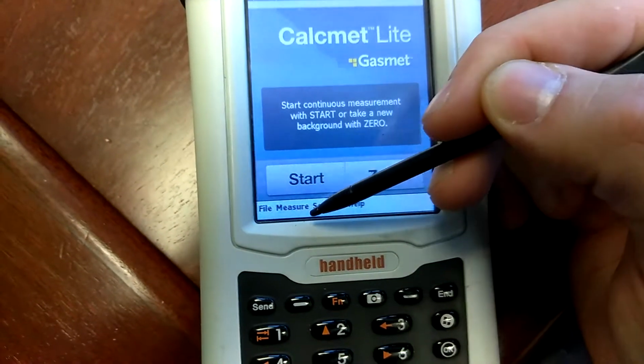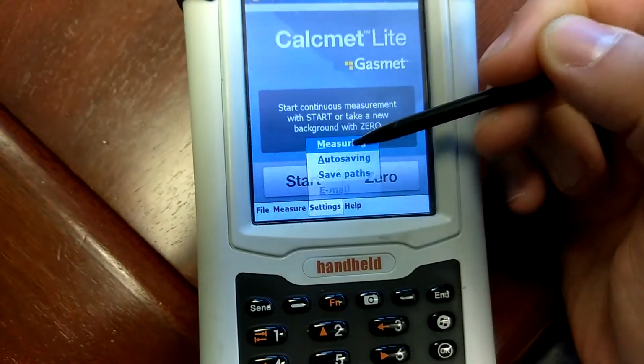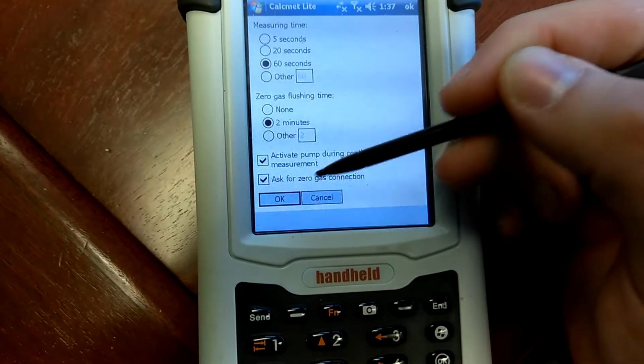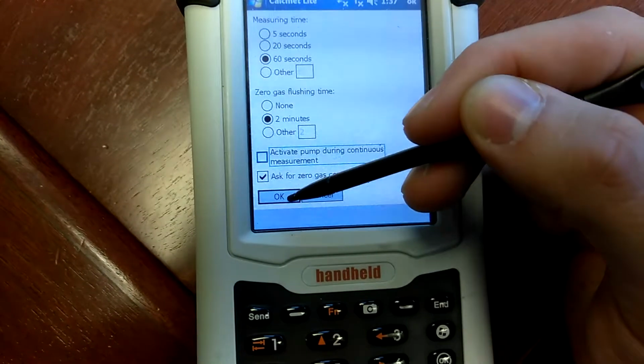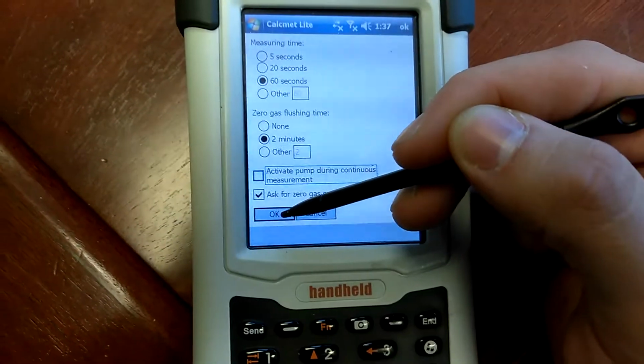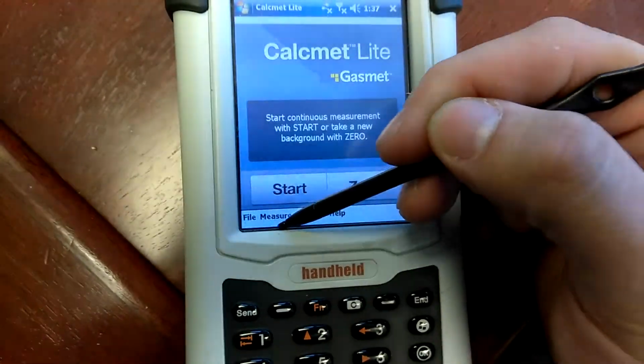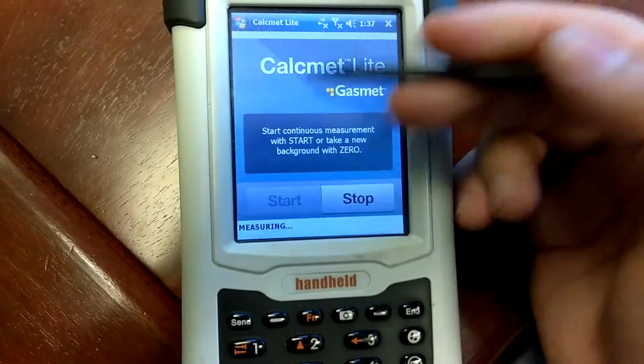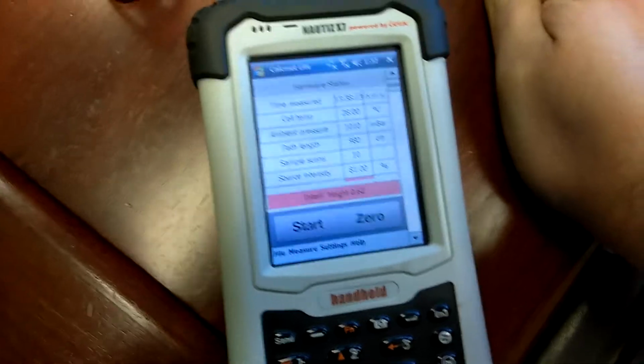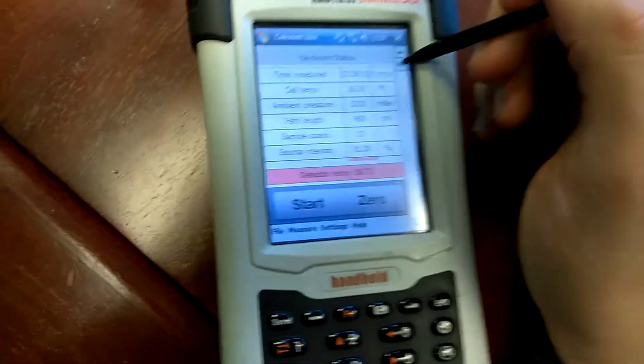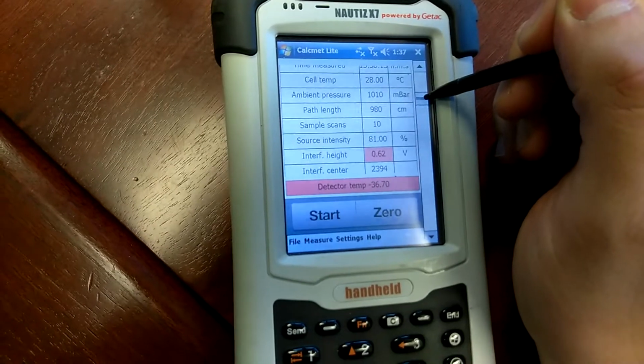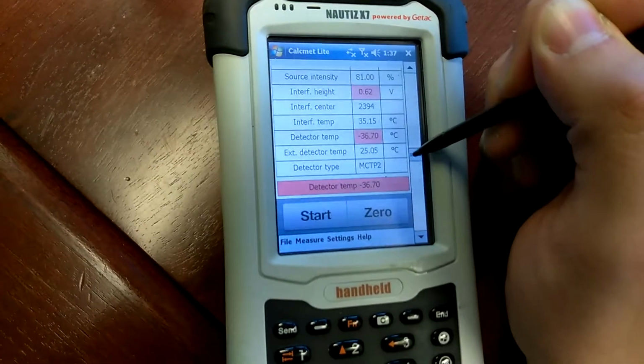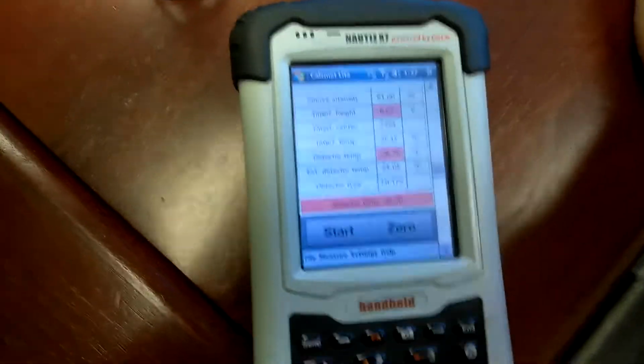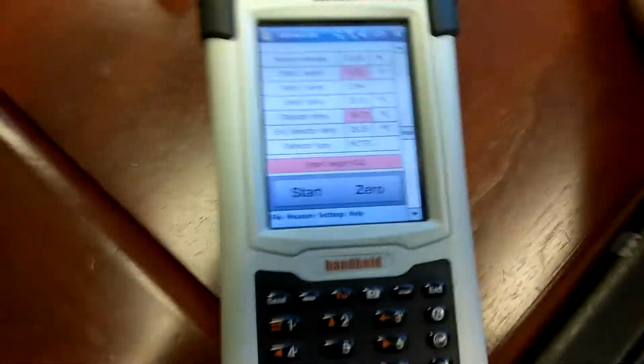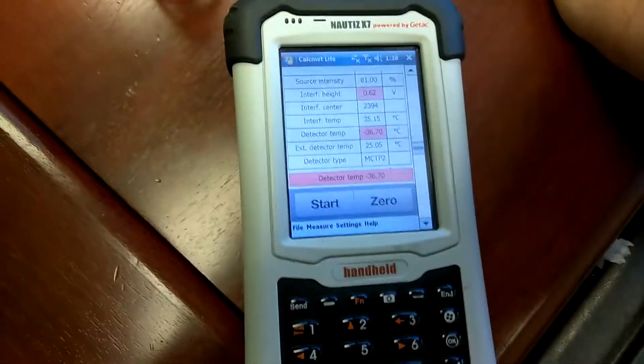The very next thing you're going to want to do is go into measuring. Make sure your activate pump during continuous measurement is off. If you don't do that, then you might have a problem later on. So go ahead and hit OK. Then we'll go to measure and then hardware status. Here's where we can determine the health of the instrument. Essentially, there should be no red on this screen. This instrument's broken. That's why we've got a weird number for interferometer height. The other thing you're really looking for is detector temp. This one hasn't been running for long enough, and it's also got a little bit of physical damage.